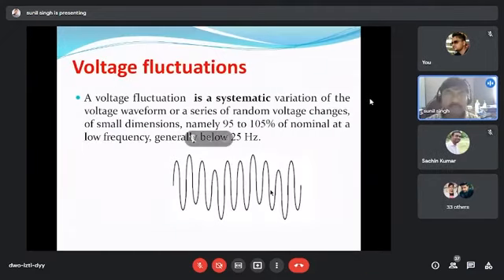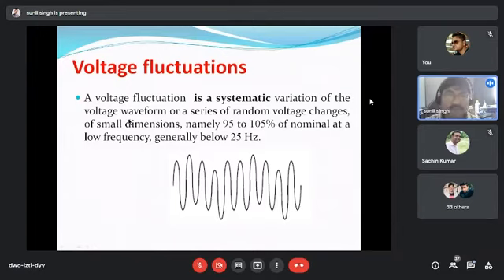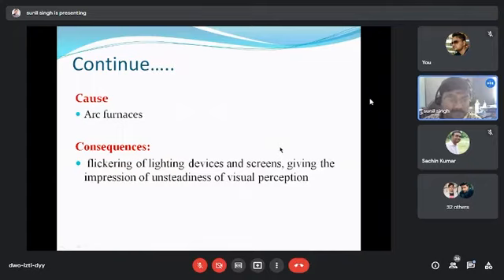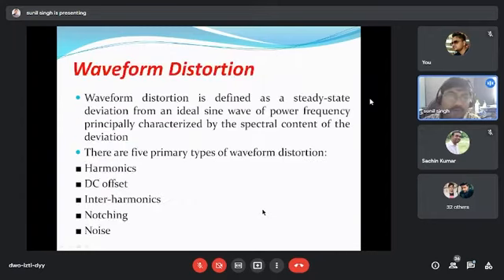Now another problem is a special type of voltage problem, the voltage fluctuation. Voltage fluctuations, or flicker, as it is called in day-to-day language. The voltage fluctuation is a systematic variation of the voltage waveform or a series of random voltage changes of small dimension, namely 95 to 105% of nominal, at a low frequency, so that it can be perceived by our eyes. It is continuous in nature. The main cause is arc furnaces or other semiconductor loads. The consequences are flickering of lights and TV screens, giving the impression of unsteadiness of visual perception, and it also affects the quality of our product.